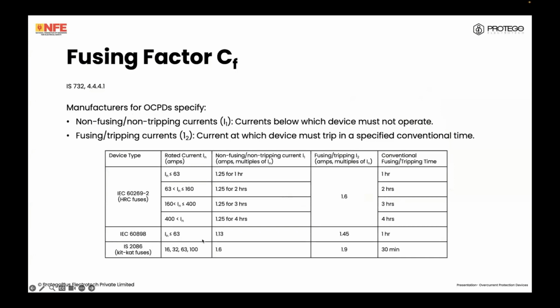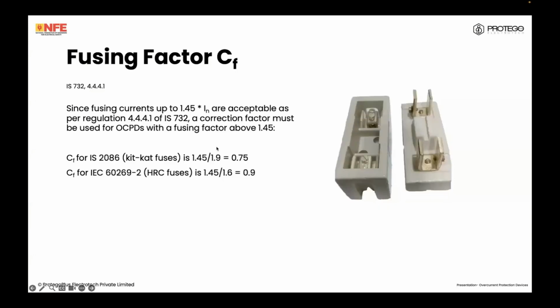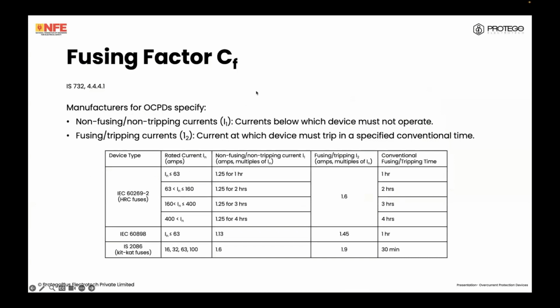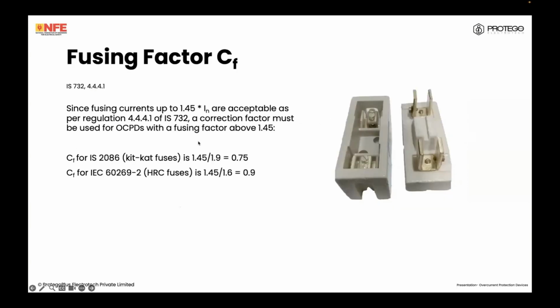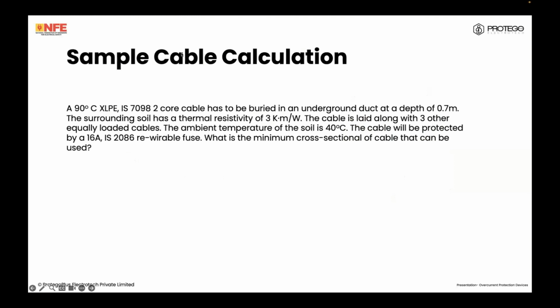MCBs to IS 60898 have a 1.45 fusing factor, so there's no derating required. If you have an MCCB, then you need to refer to your TR and your IR value. This will tell you for what current it will trip in what time. Accordingly, you take 1.45 divided by that IR, which is as a proportion of the nominal current, and then usually this is times 6, by the way, you arrive at this. So this is to do with your derating factor for fusing. Let's just run through a sample calculation.